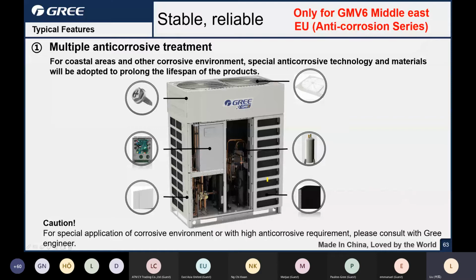And for these 2 series, we take some anti-corrosive treatment, such as the fastener, the screw, and the electric box, and the metal, and the fan grill, the grill here, and gas liquid separator, and the fin of the heat exchanger. We take some special anti-corrosive painting on the surface, so to improve the lifespan. So if your project's in the coastal areas, or the desert, or the Middle East region, or the location environment is extremely corrosive, you'd better choose this series, the Blackfin anti-corrosive series.